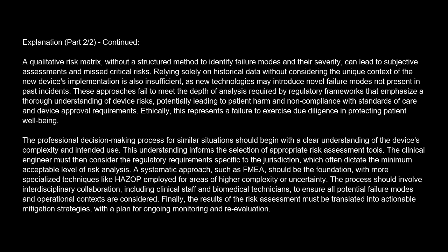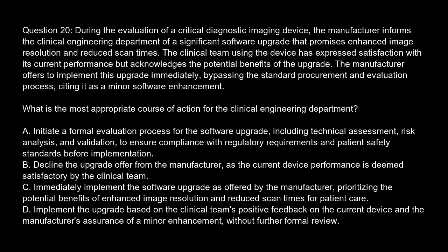The process should involve interdisciplinary collaboration, including clinical staff and biomedical technicians, to ensure all potential failure modes and operational contexts are considered. Finally, the results of the risk assessment must be translated into actionable mitigation strategies, with a plan for ongoing monitoring and re-evaluation.